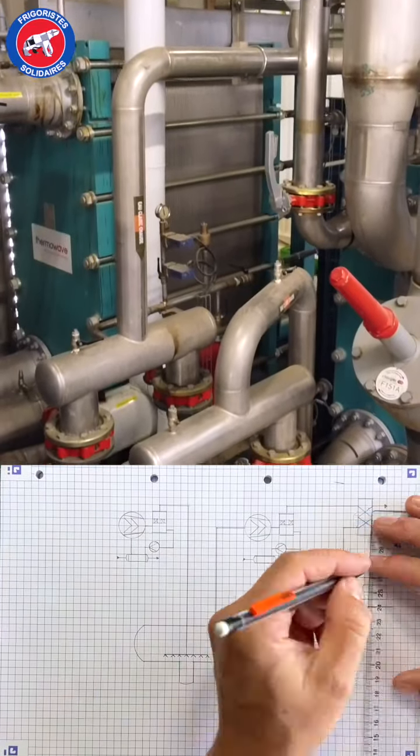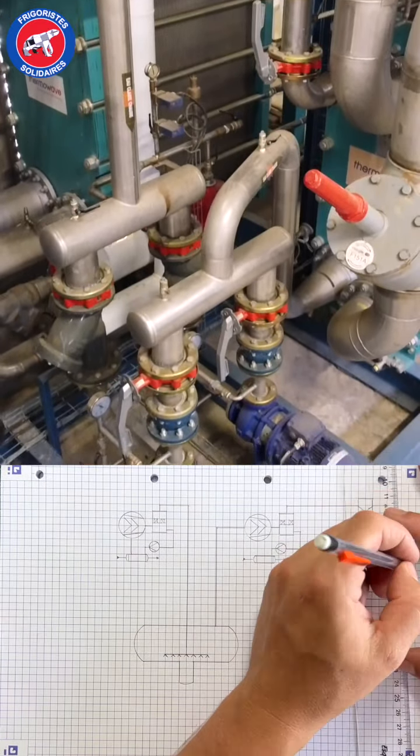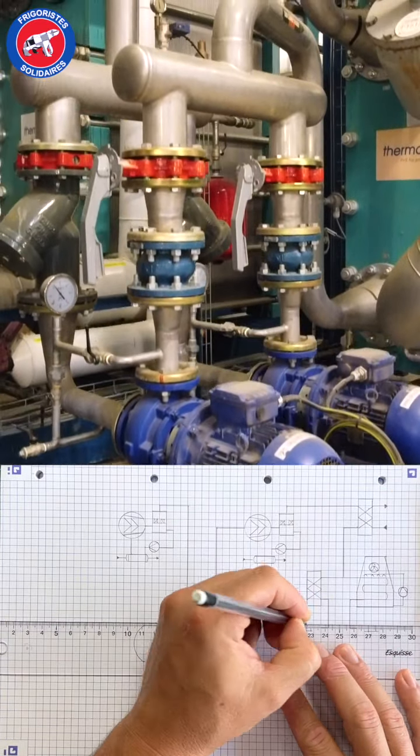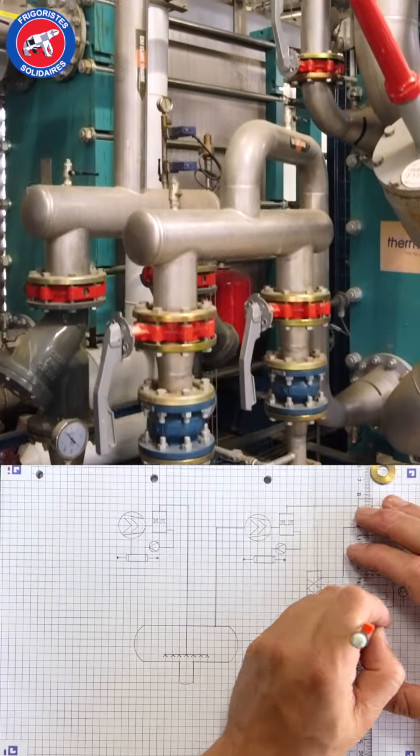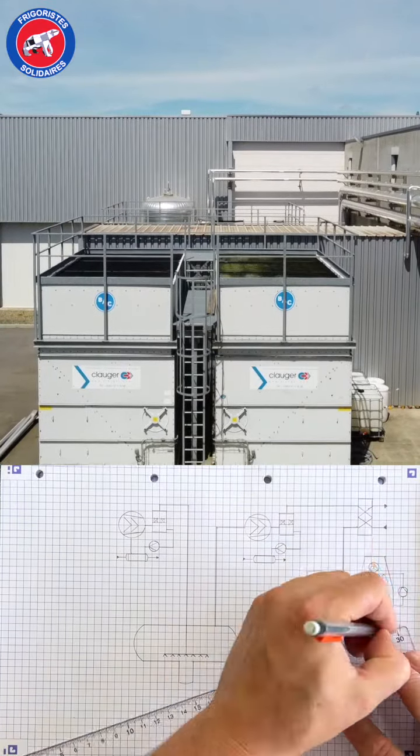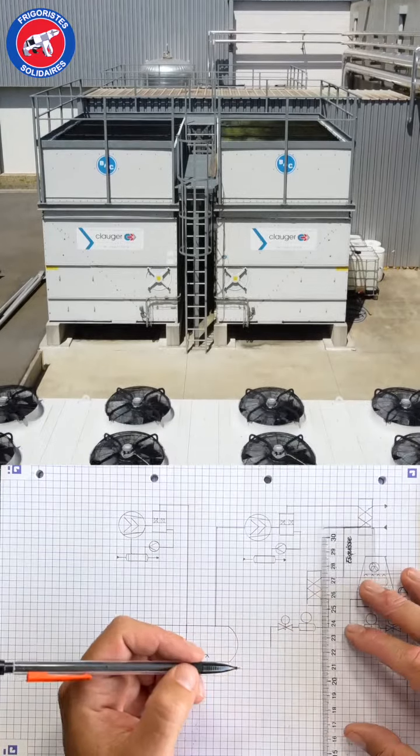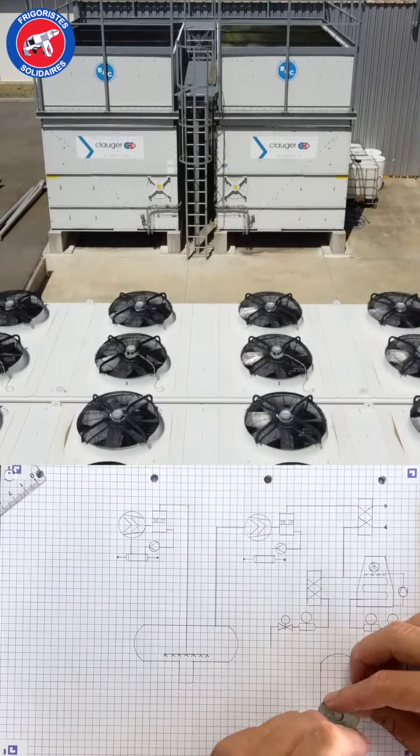A desuperheater exchanger recovers 400 kilowatts to heat water to 50 degrees C. Then the condensers evacuate the remaining energy either to pre-heat water or directly outside.